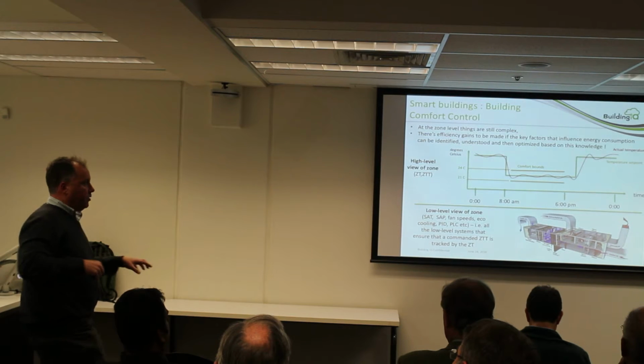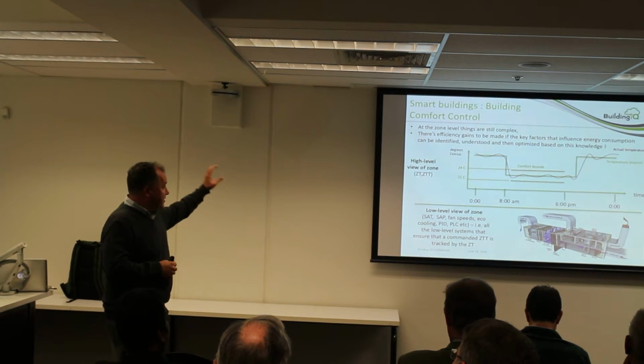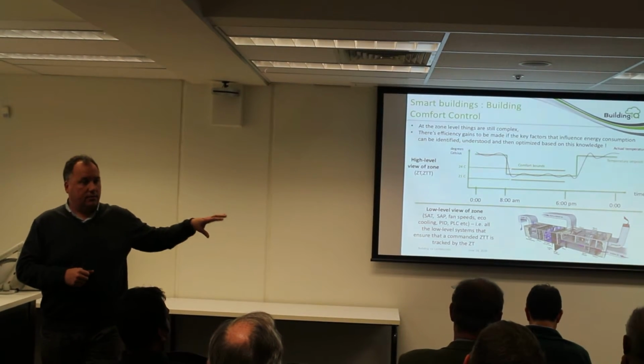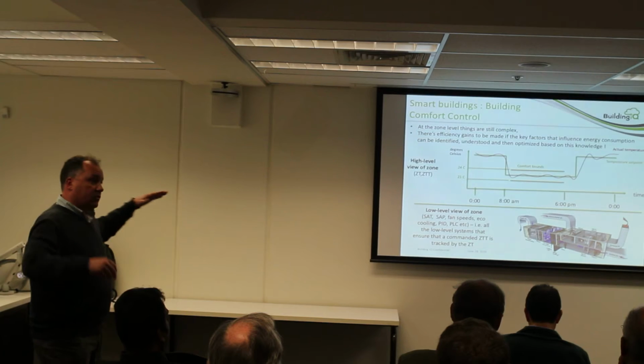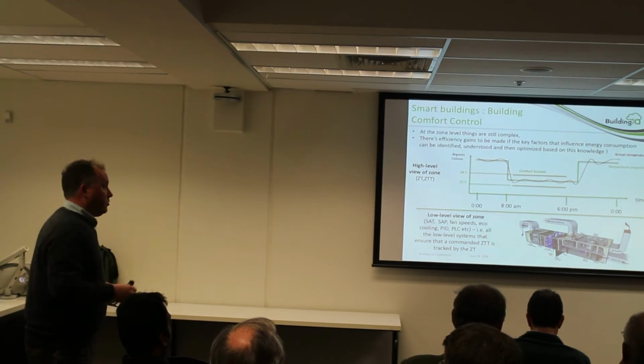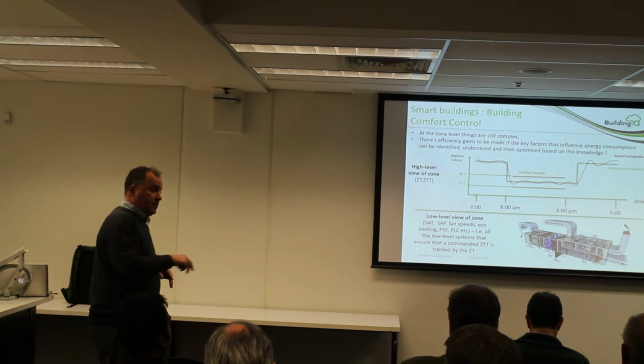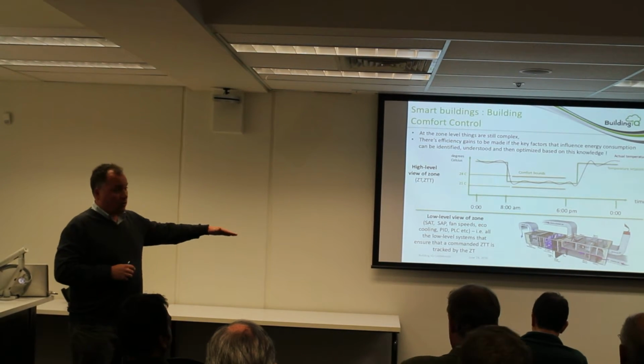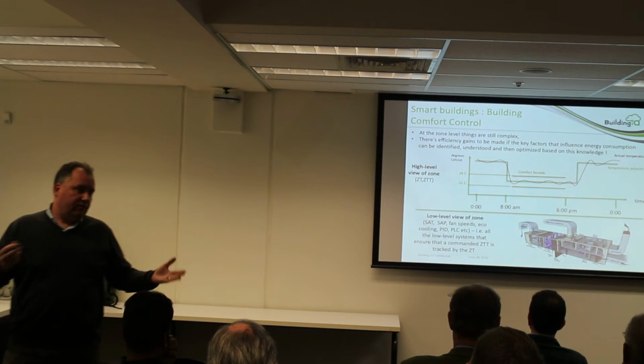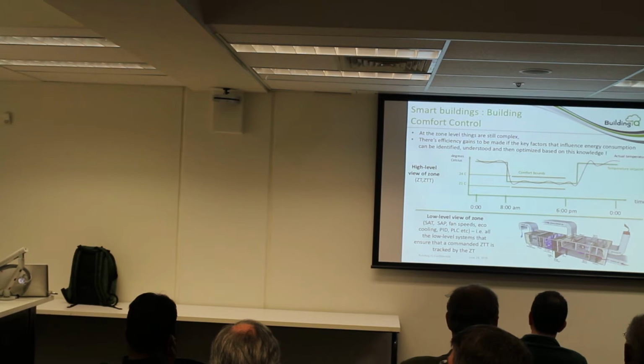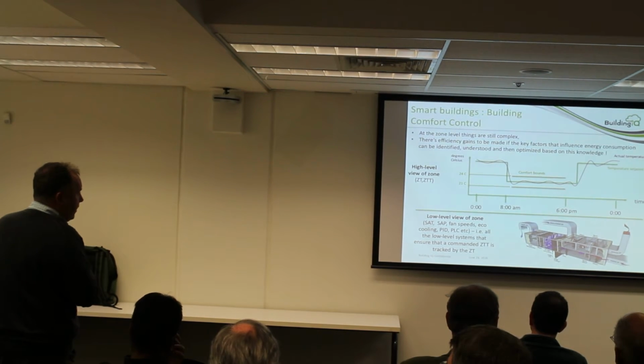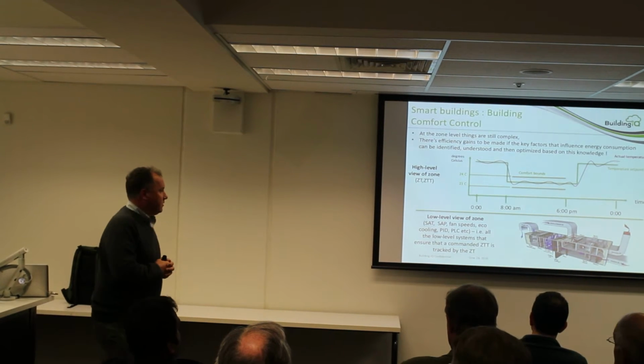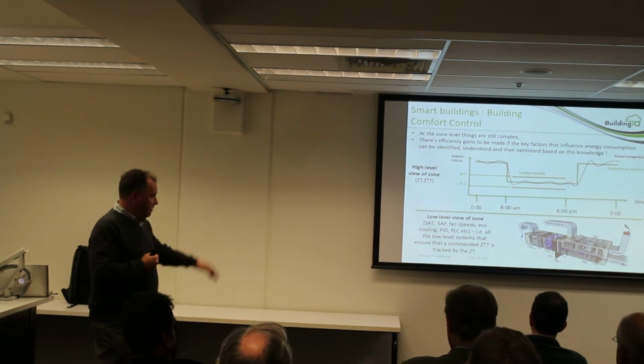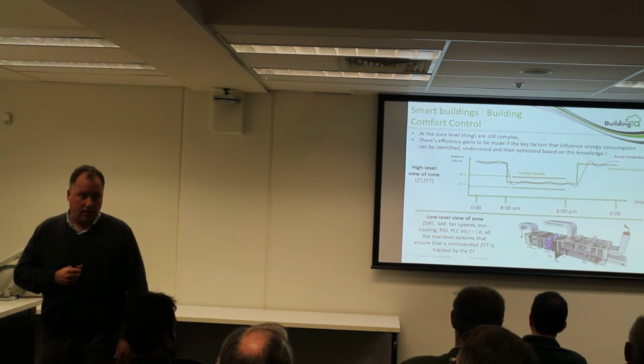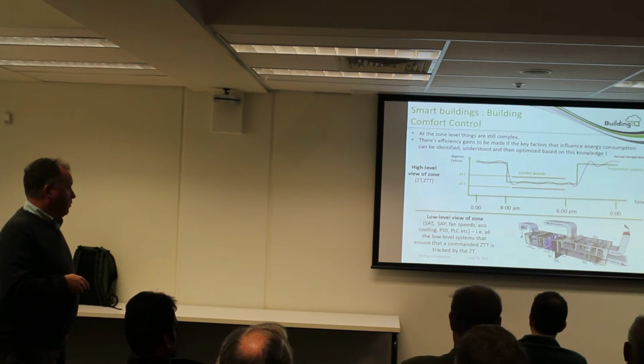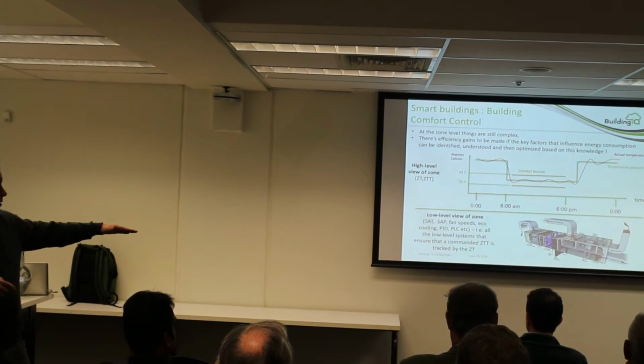We have a very small device in the building that receives those signals and acts upon that. This is high-level zone control, where we calculate the zone target temperature for each and every space. So this room, the next room, would all have their own target temperatures. That gets calculated in the cloud, sent down, and we expect the low-level zone control equipment to follow those patterns. We often find buildings aren't tuned to their specifications, people have left them unattended for a while and they've run down a little bit. We had to build a whole bunch of other tools, which I'll talk about as managed services, that help us analyze some of those faults going on in the building.